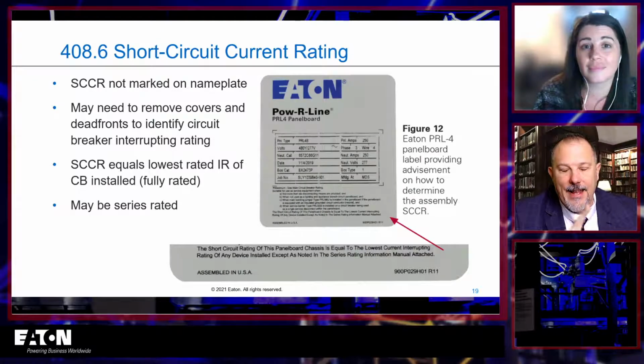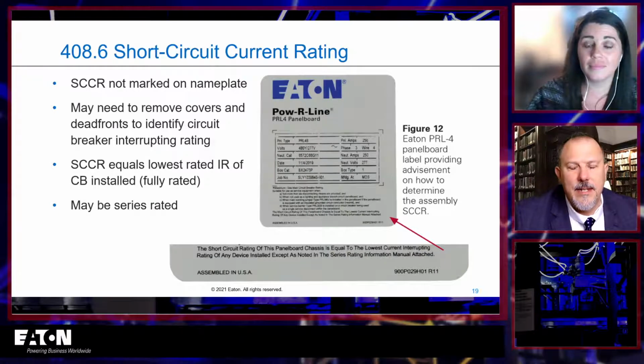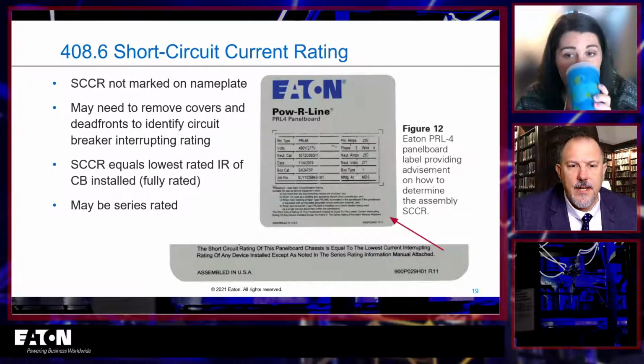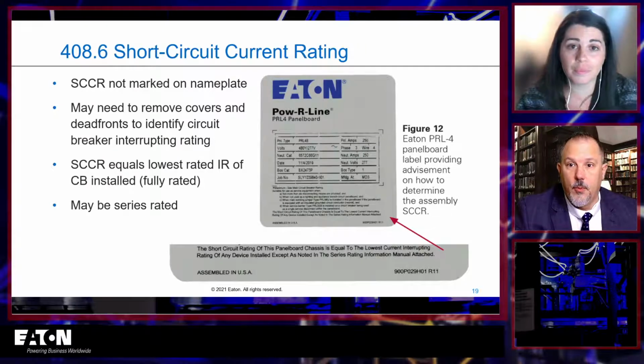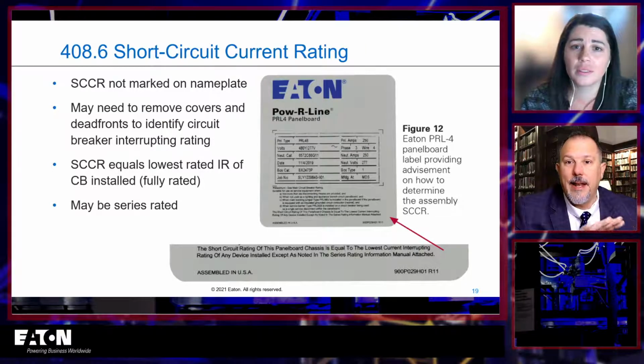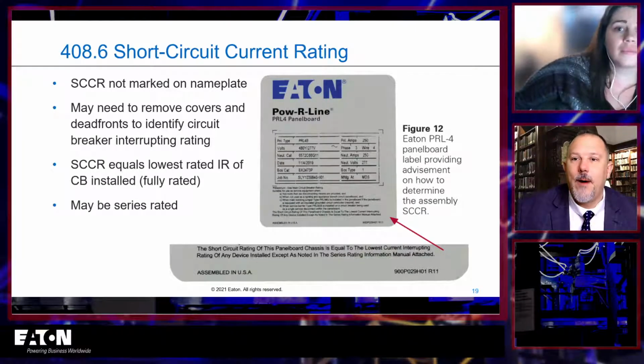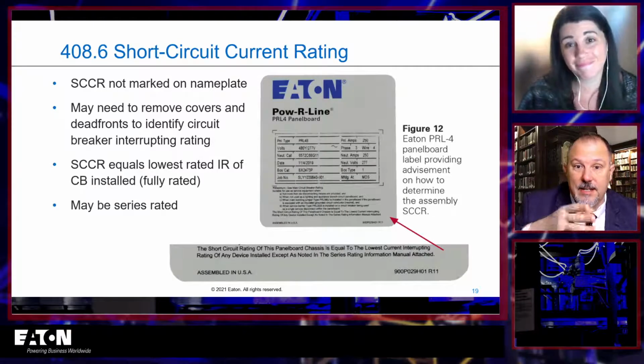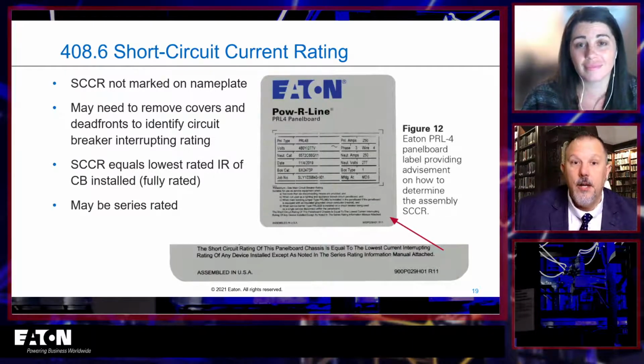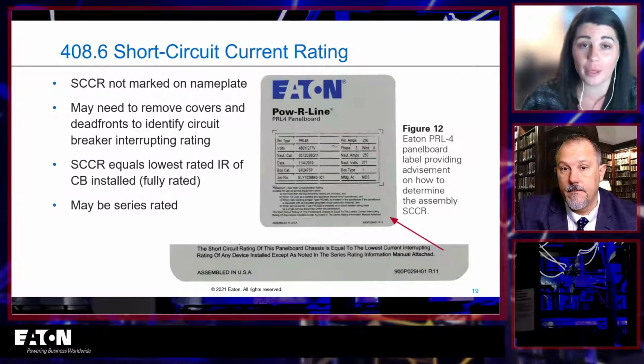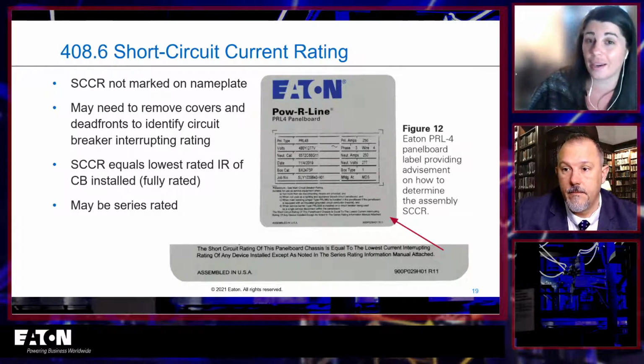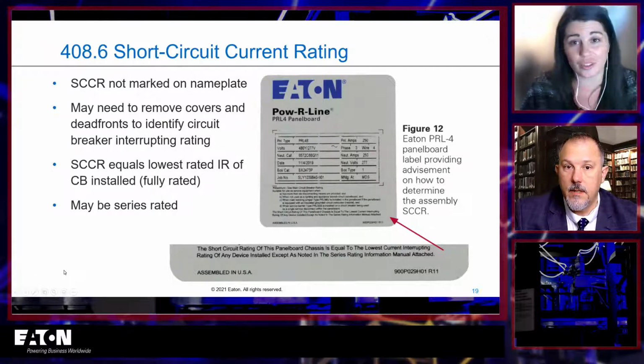So I had an idea for a public input, which I think I made or somebody made, and I'm not sure what they did with it, for this cycle to say, look, we should mark a panel board short circuit current rating on it. And a lot of times when I say we should mark it, they'll say, well, Tom, it's already required to have that and it's part of the listing. But to your point, Christy, I call it a recipe, not a rating, because it tells you how to determine it. It doesn't tell you what it actually is. Yeah, it's not written on the panel board label. It's not actually required.